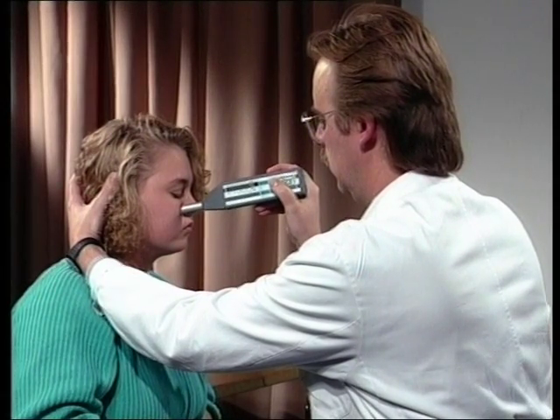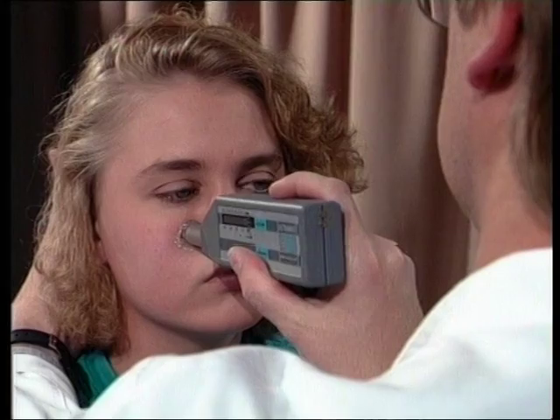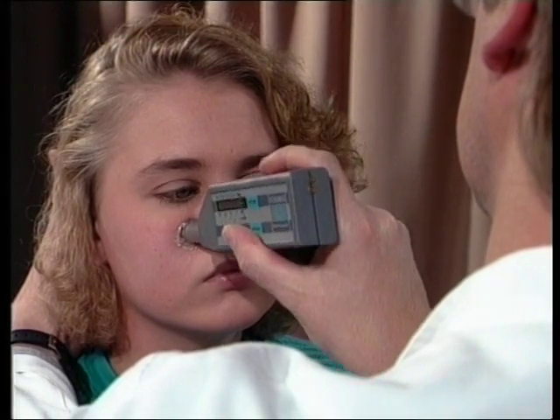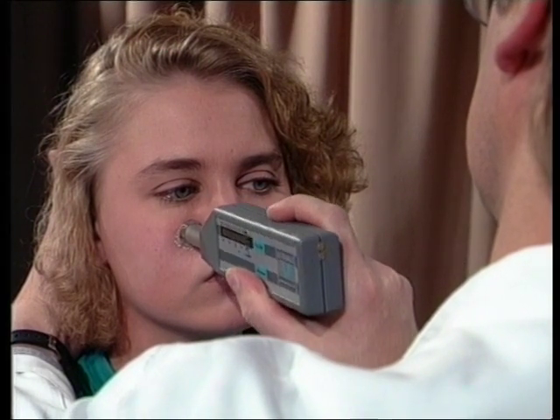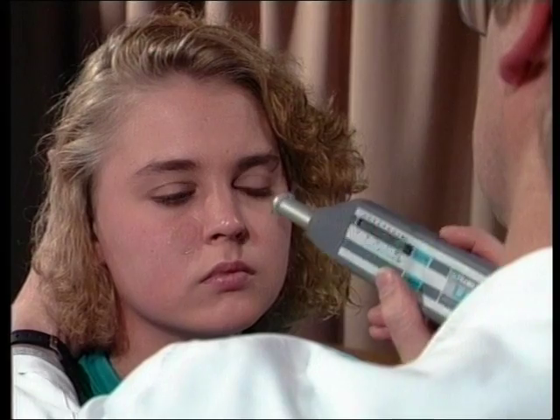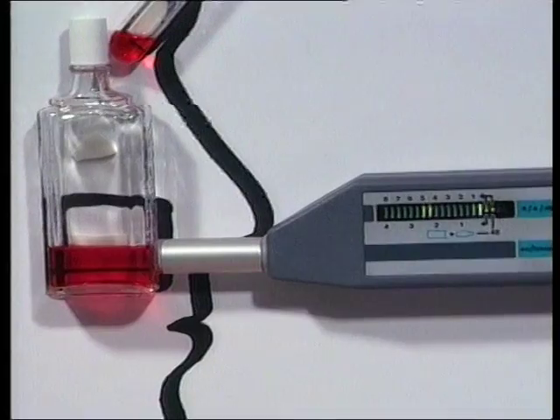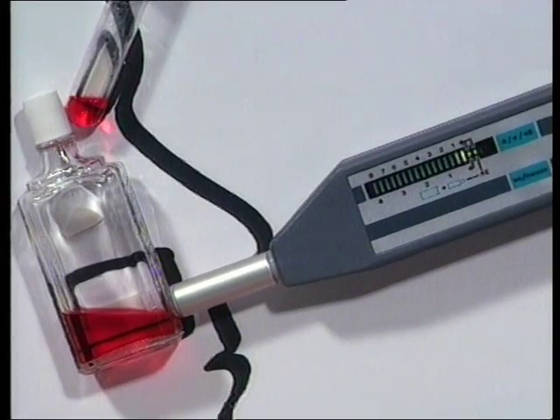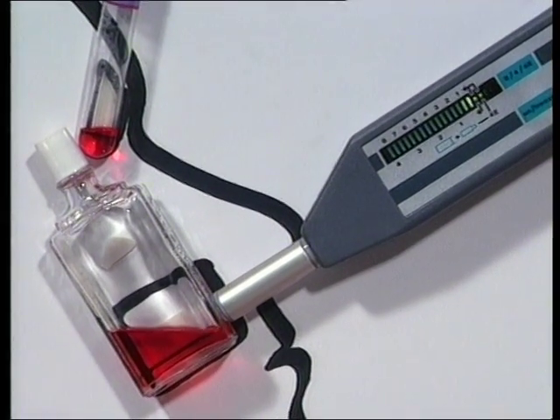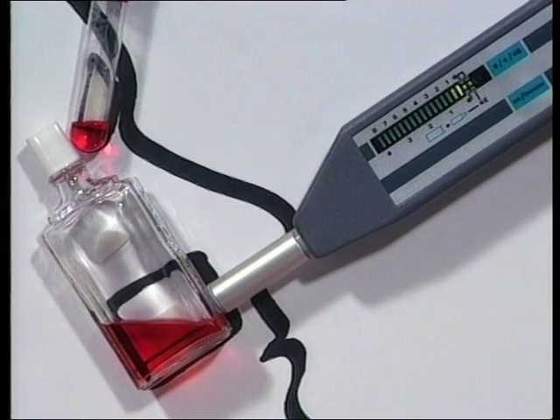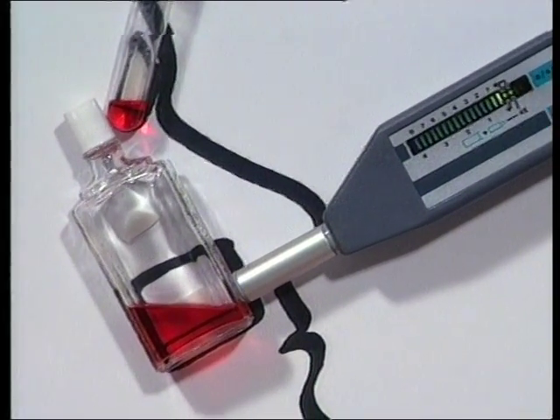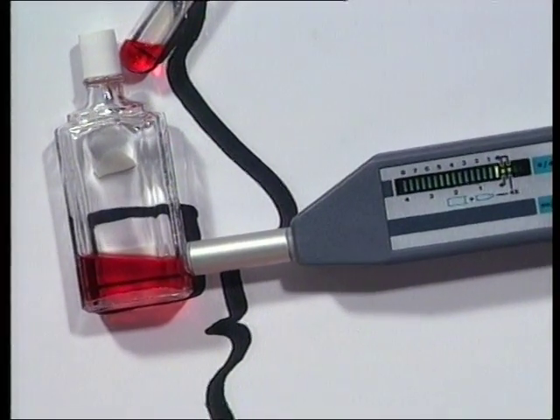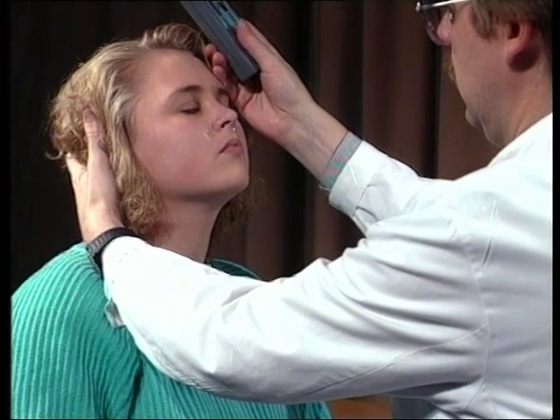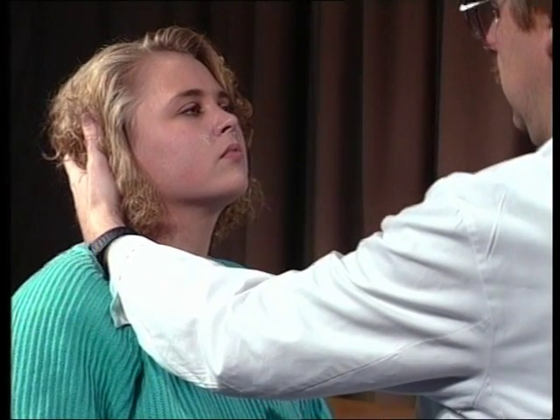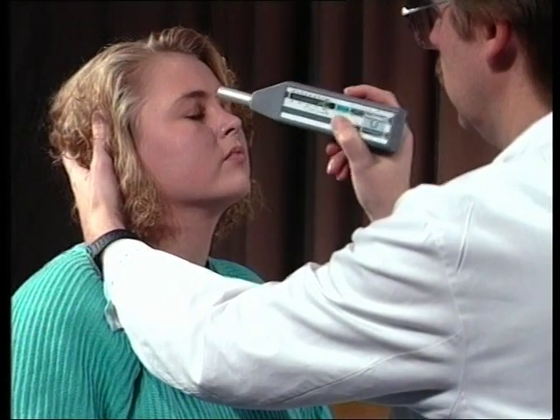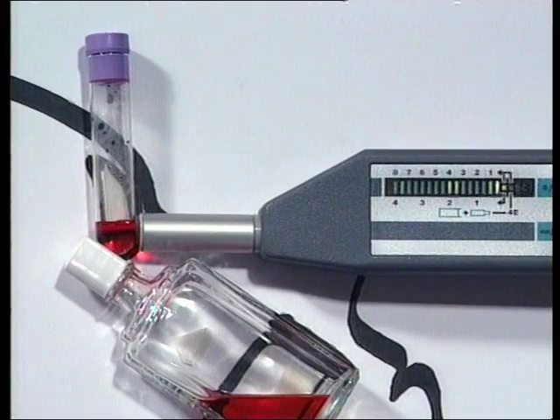To acquire the right examination technique, the following points should be kept in mind. When scanning maxillary sinuses, the patient's head should be upright in order to prevent any secretion from flowing towards the back of the cavity. It can be seen in this schematic model that the continuity of the fluid between the anterior and posterior wall is interrupted when the patient's head is tilted backwards. When scanning frontal sinuses, however, the patient's head must be tilted backwards 30 degrees so that the exudate forms a connection between the anterior and posterior walls.